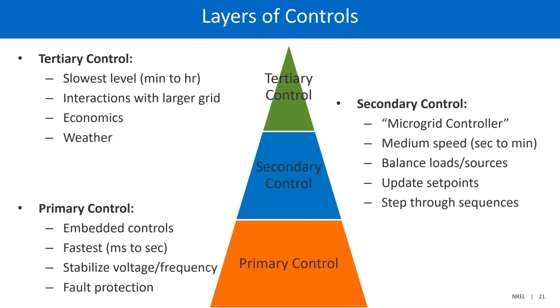Below that is the primary control. The primary controllers are typically embedded in all of the components, items like a generator controller or a programmable logic controller. There are a lot of different components that fit in this category. They're very fast, typically milliseconds to seconds, with the primary goal of stabilizing voltage and frequency across the grid and providing fault protection, but they respond first.